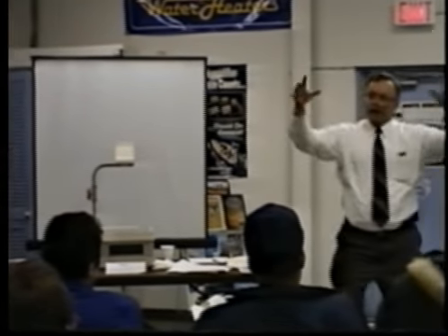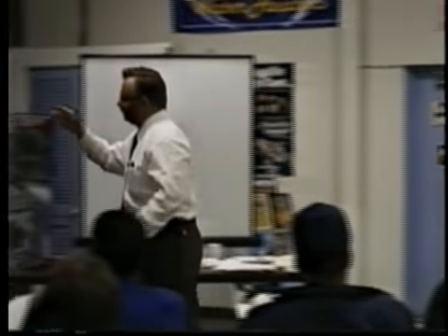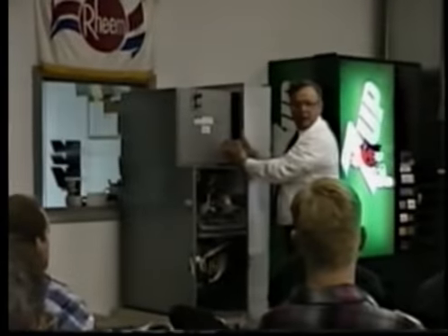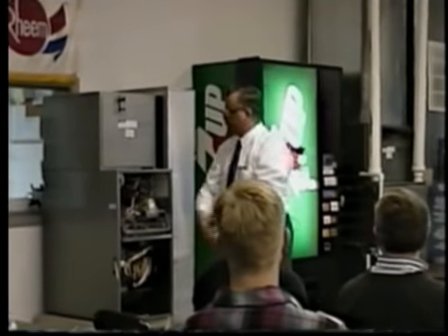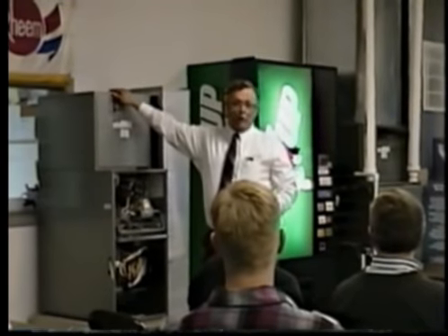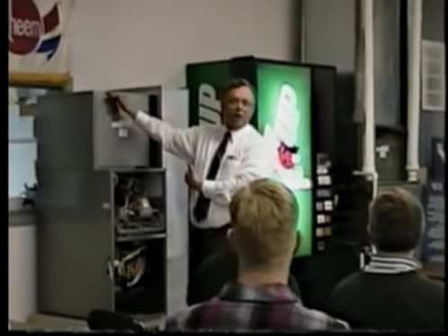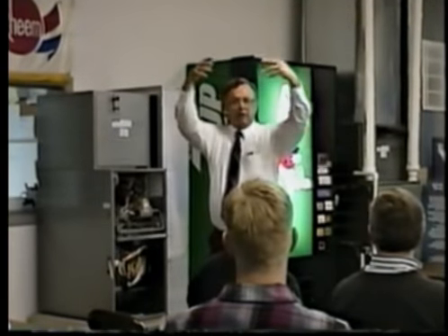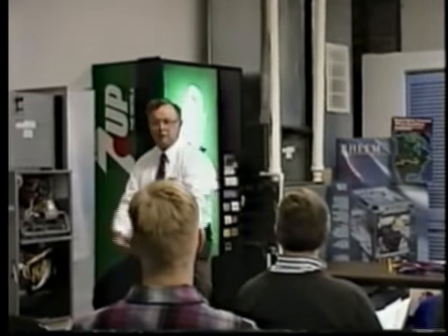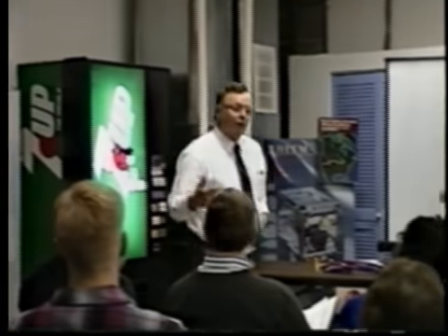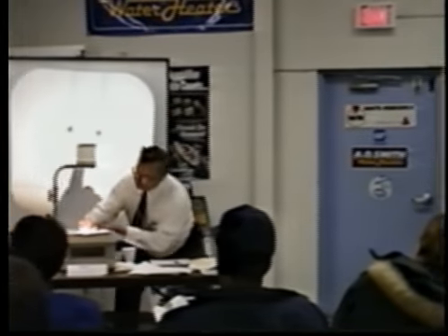When we're in a home and we're trying to cool it, don't we take a lot of hot air? And right here, this would be an air conditioner in a home. If we take a lot of hot air and try to cool it, we have to run it through a coil that sits here, and the coil is cold. The coil's about 40 degrees, and maybe the air coming back to it is 100 degrees. So actually the air gives up the heat to the cold coil by running it through the coil, and that's how we cool the air. Is that really important? Yeah, because of this.